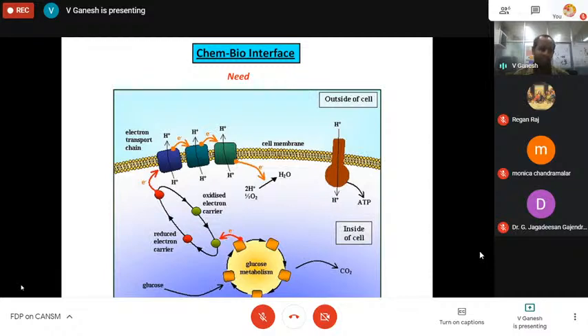How does that instrument work? Well, the flexible and disposable strip has an enzyme called glucose oxidase, which specifically oxidizes glucose to gluconic acid and hydrogen peroxide. The moment you insert that strip into a device, the device, using electrochemistry, can either oxidize or reduce hydrogen peroxide, and in turn will measure how much current is produced during this reaction, so you are able to measure how much hydrogen peroxide is produced. In turn, you can correlate how much glucose is there in your blood serum sample through the enzymatic reaction. In fact, that's how the instrument works.